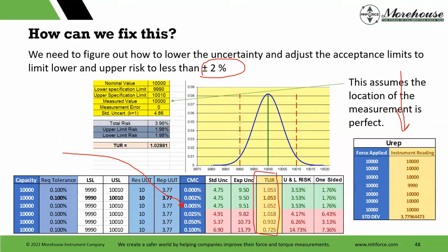Choosing the right equipment. The only way to lower total risk is by a scale with better repeatability and resolution. Changing the process may cause all kinds of measurement problems, resulting in much higher risk. So here you have a thing. Maybe you're using a cal provider with dead weights and you like the price of someone with load cells. Someone goes, hey, I got this great price on calibration. I think we should send all our equipment there. It may make sense to do that.